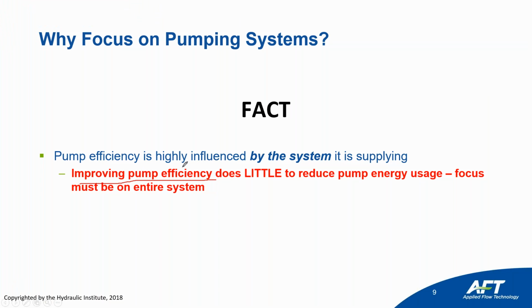They're usually just saying stick a VFD or a VSD on your pump and that will solve all your problems. No, it won't. The thing is, if you put a variable speed drive or a variable frequency drive on a pump, that can help. That way your pump is not just constantly operating at 100% speed no matter what. It can adjust better to the operating conditions. But the major issue is you have to look at the system itself.